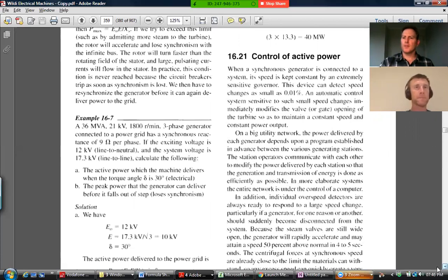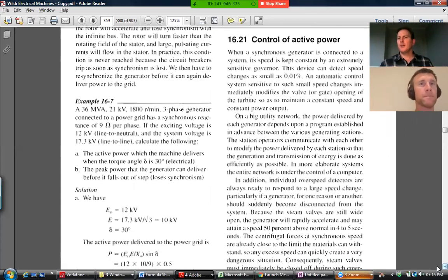So there are things controlling the speed of all of these, and if they see the speeds starting to drop, there's some massive control room somewhere which says, start shutting off Auckland, places that are not really necessary, drop them off the grid so that we can bounce back. Otherwise, everything starts to slow down or voltages start to dip. So yeah, some load shedding. Under frequency load shedding.